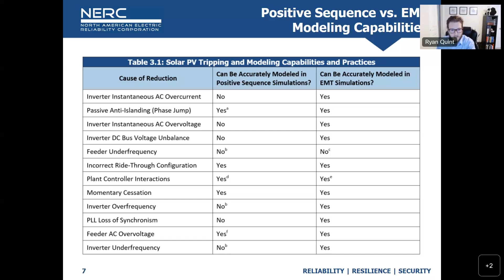Now let's go a step further—again, can those models recreate the causes of reduction we saw in the 2022 event? Look around that pie chart: there's a whole lot of no's, and those no's are on the big ones. That's because of instantaneous protections that happen sub-cycle, sub-millisecond even, protections that really aren't represented in the dynamic models available to transmission planners today for positive sequence. So there's that aspect of, well, no, I can't represent it.